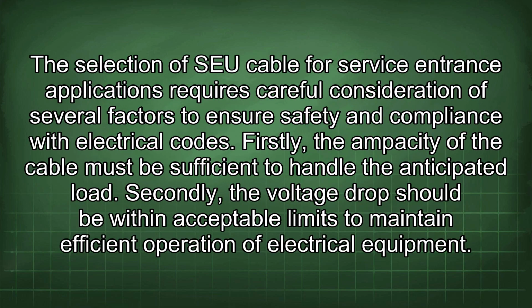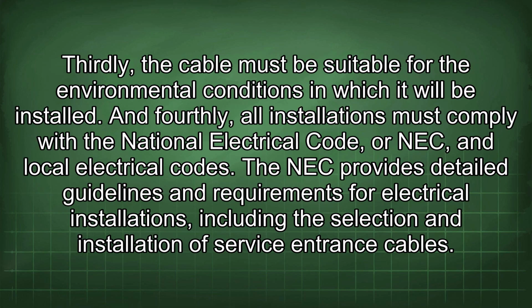The selection of SEU cable for service entrance applications requires careful consideration of several factors to ensure safety and compliance with the electrical codes. Firstly, the ampacity of the cable must be sufficient to handle the anticipated load. Secondly, the voltage drop should be within acceptable limits to maintain efficient operation of electrical equipment. Thirdly, the cable must be suitable for the environmental conditions in which it will be installed. And fourthly, all installations must comply with the National Electrical Code, or NEC, and local electrical codes. The NEC provides detailed guidelines and requirements for electrical installations, including the selection and installation of service entrance cables.